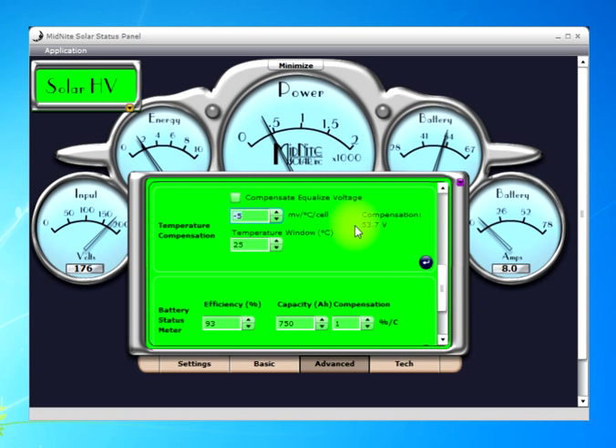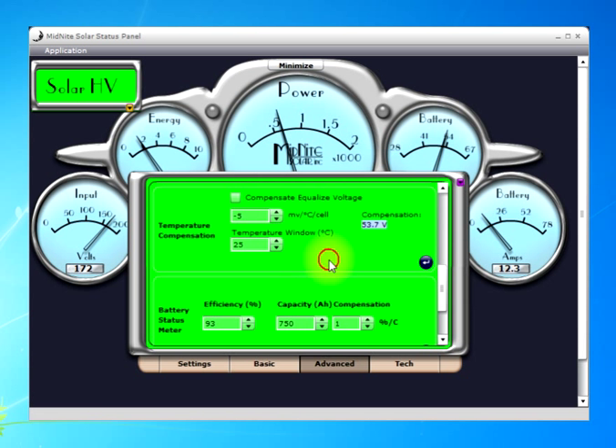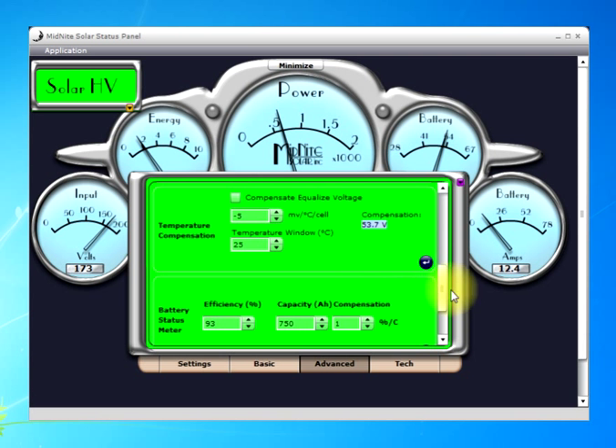This number up here relates to voltage — it's the millivolts per degree C per cell that compensates the voltage we're targeting because of that 25 degree reference. In my case, my batteries are running about 10 degrees C, so it's going to elevate the voltage quite a bit. Once those two parameters are set, you click this button to write those values to the Classic.